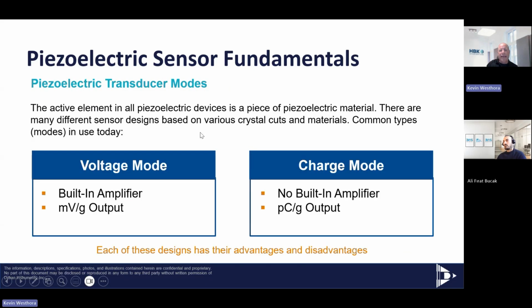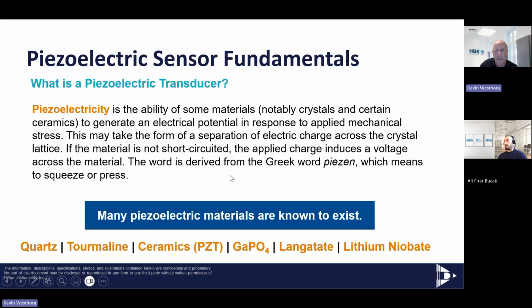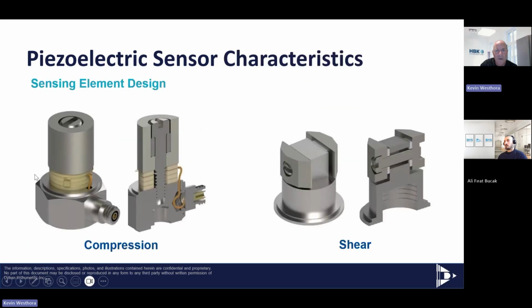Now that we know what a piezoelectric transducer is, let's talk about the two different types of sensors. A piezoelectric charge mode accelerometer means there's no amplifier in the sensor. On the left here is a charge mode accelerometer—just a stack of crystals, no amplifier at all. If I shake this accelerometer with no voltage, no power supply, I get an output. It's called self-generating. The problem is, it's a picocoulomb output, and not very many data acquisition systems can read picocoulombs.